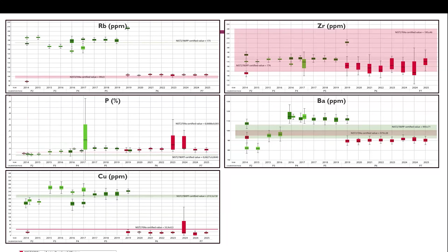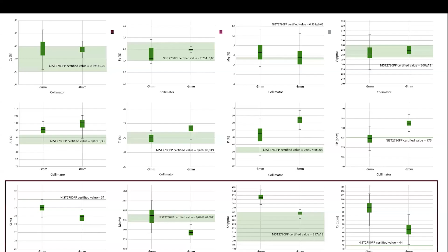Now I go to the collimator effect, to the impact of the collimator effect on the results, to be able to take into consideration the impact of using a 3 millimeter spot on the analysis of samples. We could see from the results that most elements don't have changed values, whether the 8 millimeter or 3 millimeter spot is used for the analysis. However, some elements show higher quantification with the 8 millimeter spot, while others show lower value. These variations, especially for these samples, do not necessarily indicate better or worse results or accuracy obtained by one spot more than the other.